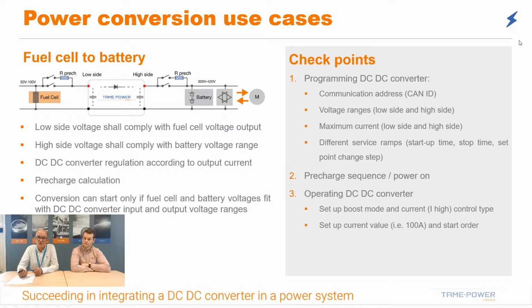It is connected to the other devices through a precharge, because as represented here, you have internal capacitors in the DC-DC converter. So when you connect a voltage source or any source to the DC-DC converter, there is an inrush current incoming at the very moment where you connect the source to this capacitor. This would lead to an inrush current that could destroy your connection, your connectors, your wires, and that could also destroy some devices inside the converter.